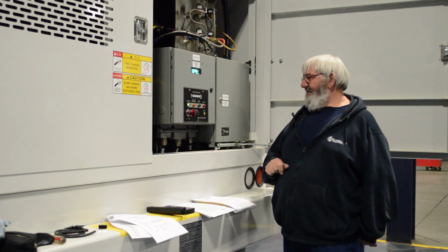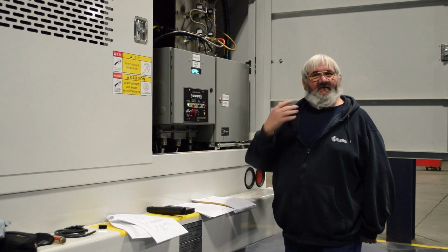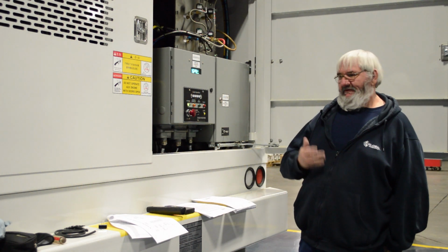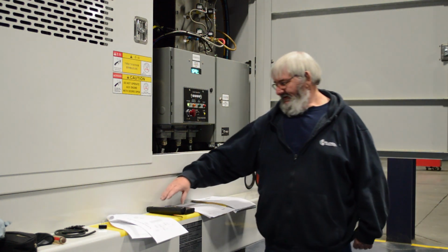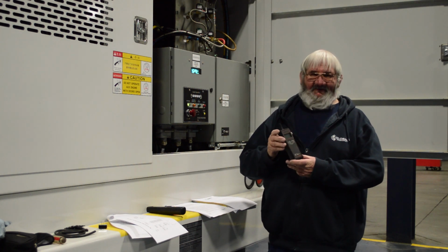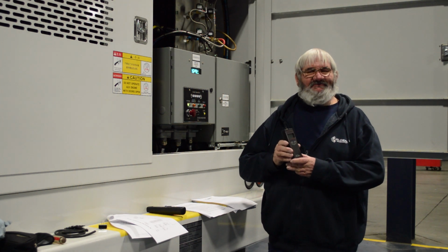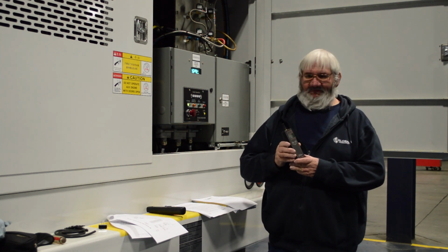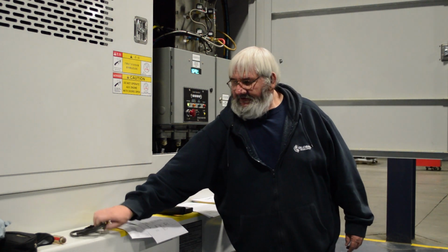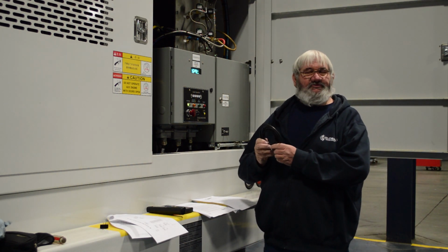Now from here we're going to troubleshoot each of the two areas that we need to look at, our fuel and our blower. Now a couple of things that will help you troubleshoot on the blower side. One is a manometer. The manometer actually measures air pressure. I say air pressure, it's actually inch columns of water in the burn chamber. You would use the hoses to connect your manometer. We would connect this up to the air pressure transducer.